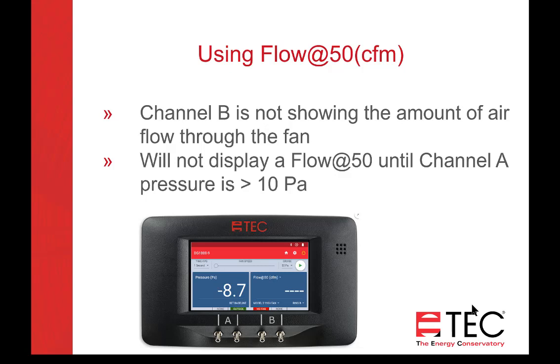So in this case, Channel B is on, and we've got the fan cranked all the way up, and we're only able to get up to negative 8.7 pascals, so we don't have a flow shown. If we switch from flow at 50 to the flow mode, now it will display the flow through the fan.